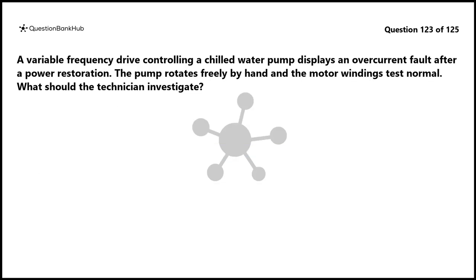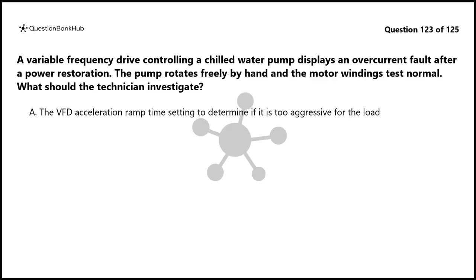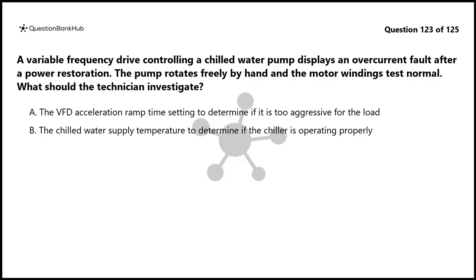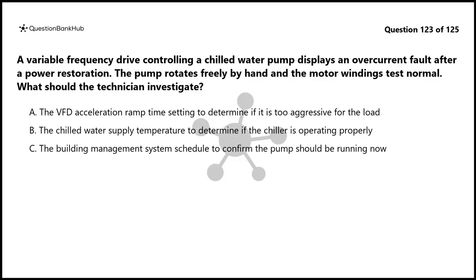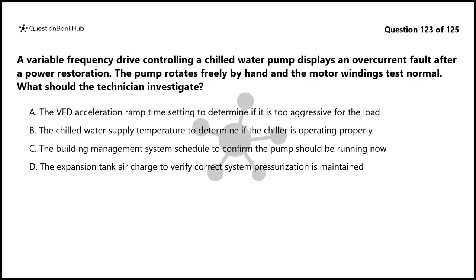Question 123. A variable frequency drive controlling a chilled water pump displays an overcurrent fault after a power restoration. The pump rotates freely by hand and the motor windings test normal. What should the technician investigate? A. The VFD acceleration ramp time setting to determine if it is too aggressive for the load. B. The chilled water supply temperature to determine if the chiller is operating properly. C. The building management system schedule to confirm the pump should be running now. D. The expansion tank air charge to verify correct system pressurization is maintained.